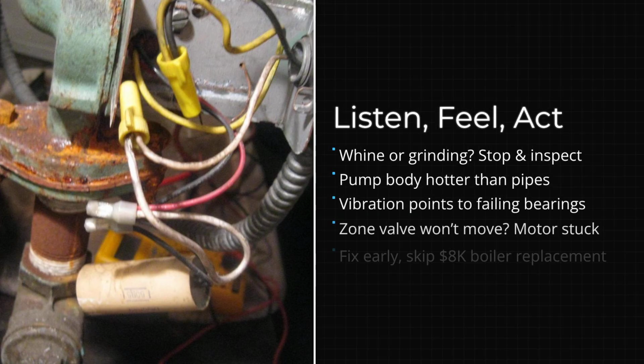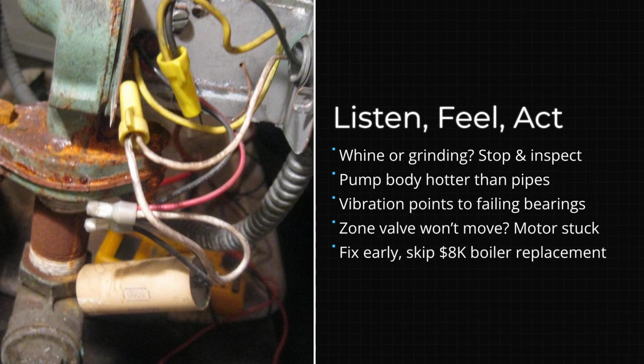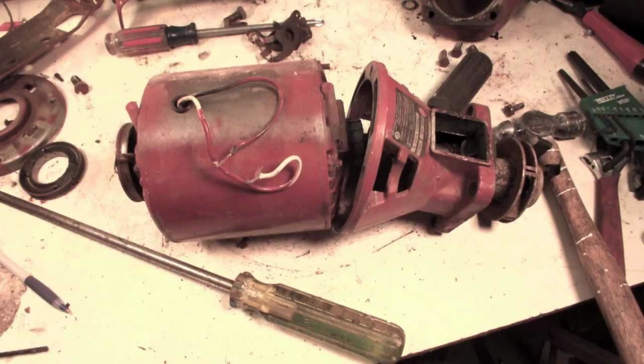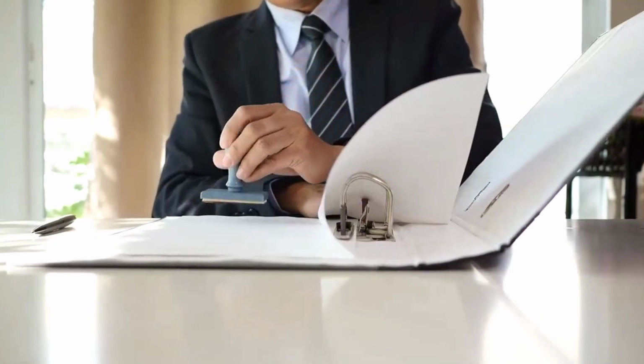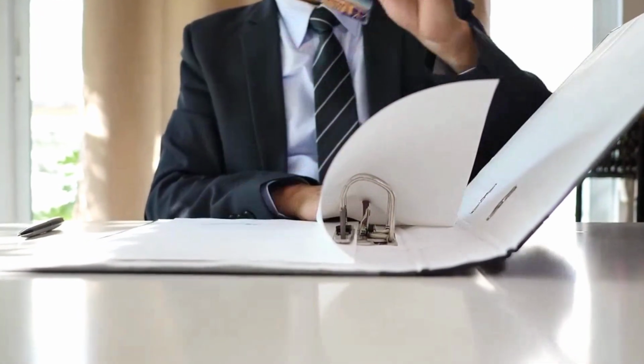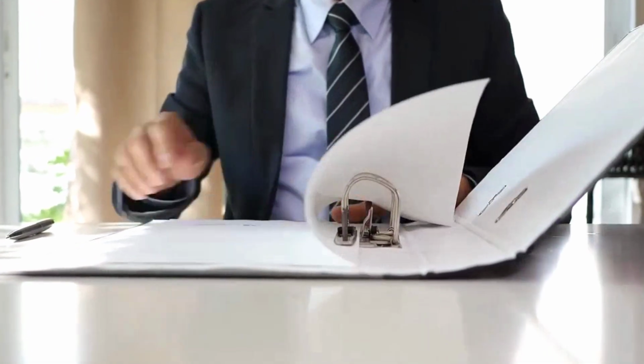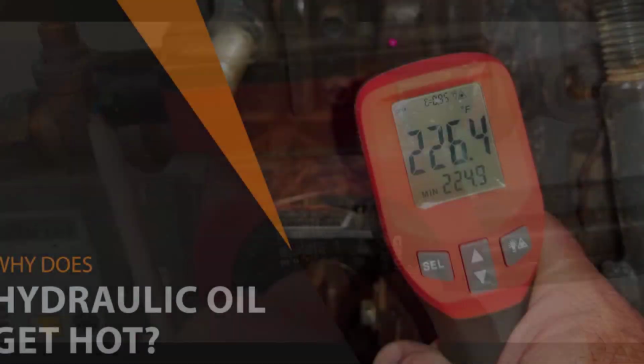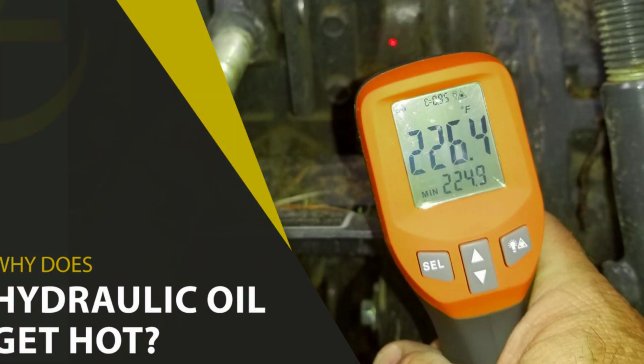Start with your senses. Hear a high-pitched whine, a low grinding rumble, or feel the pump body hotter than the pipes. That is not normal. That is bearing wear or a motor running dry, and it is the first clue you are about to be upsold on a new boiler. Put your hand on the pump. Vibration or a hot case means the bearings are crying out for help.